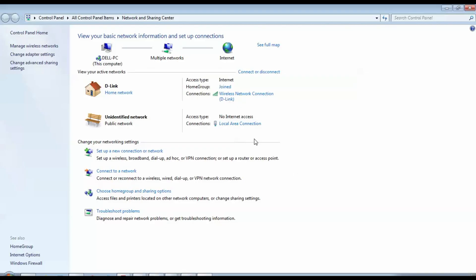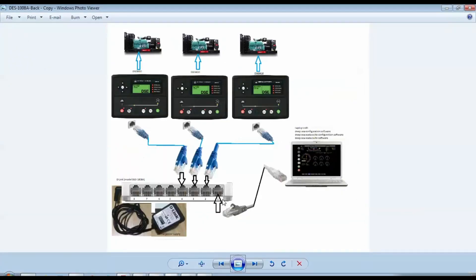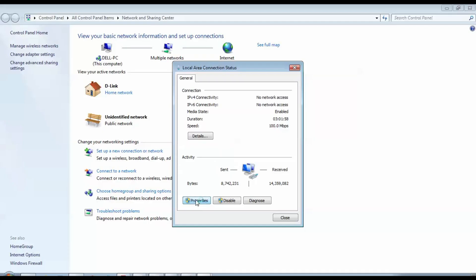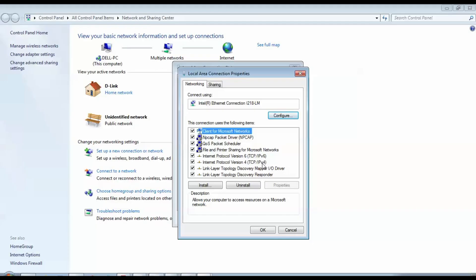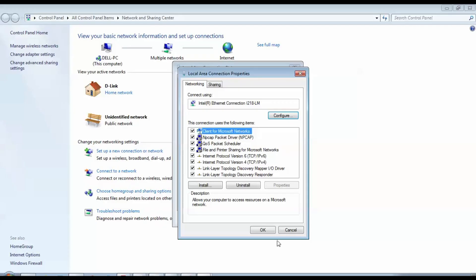Step 2: Configuring the Laptop Network. Next, we must configure the laptop's network. Go to Network and Sharing Center. Connect the laptop LAN cable to the D-Link switch. If disconnected, the local area connection disappears; when reconnected, it reappears. Open Properties > Internet Protocol Version 4. Set IP address to 192.168.1.99, subnet mask 255.255.255.0. Click OK, then Close. Now the laptop is ready to communicate with controllers via the switch.